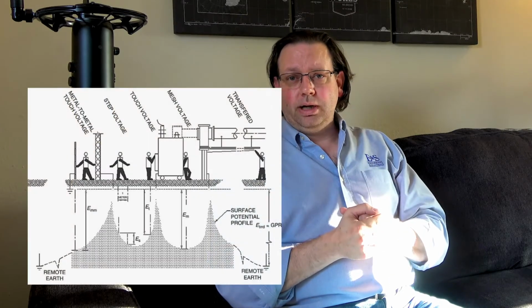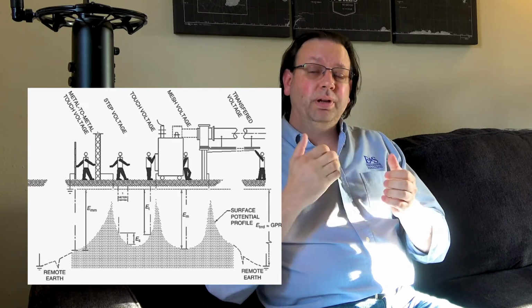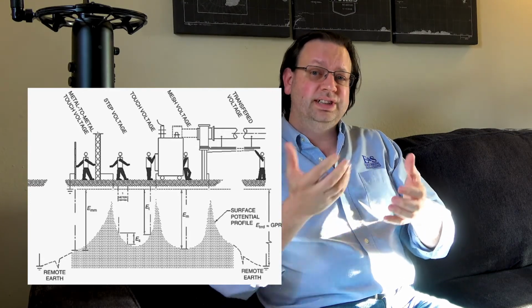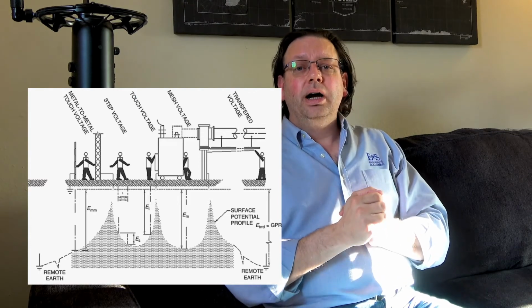It's a very complicated topic. You obviously need to design your grounding systems and place the specs for those grounding systems in accordance with the systems you're designing that grid for. But before you go slapping down resistance to ground specifications, please figure out whether or not you really need a low resistance to ground, because a grounding system that works in clay and one that works in solid rock could be the exact same system, and they could work very well and have very different resistances to ground. One could be very low and one could be very high. And they can both be super efficient, super effective grounding systems, because again, the resistance to ground isn't the primary driving factor for most grounding systems.